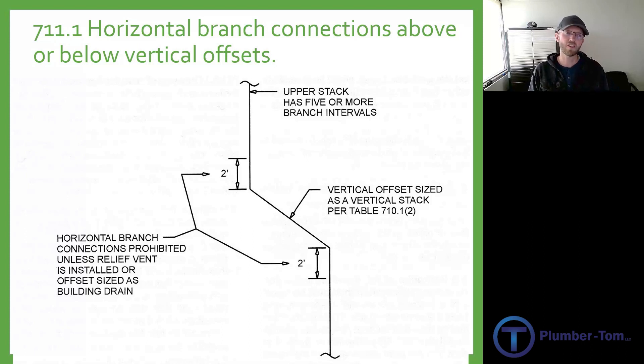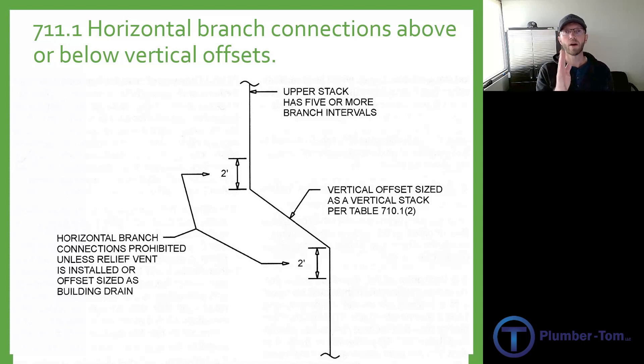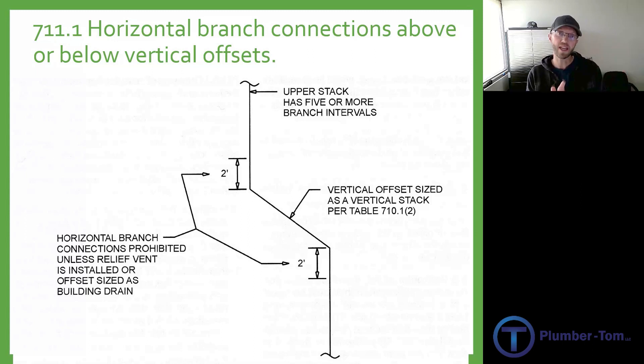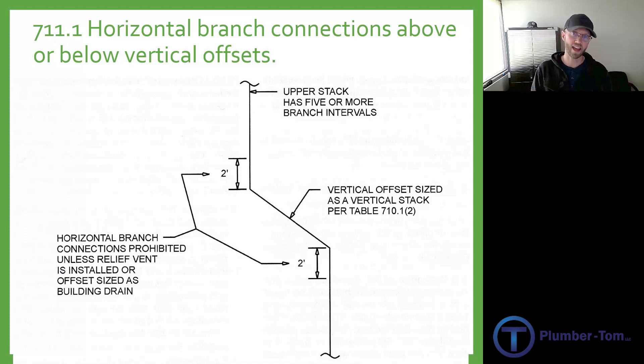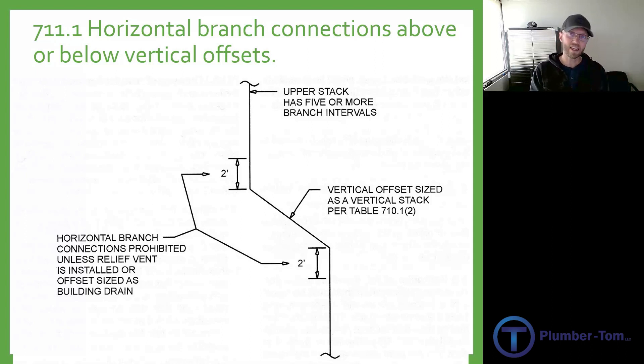7-11.1 talks about horizontal branch connections above or below vertical offsets on a stack. A stack is a vertical drain pipe. As it's coming down it needs to move over — this is called an offset. A vertical pipe is any pipe that is straight up or down to a 45-degree angle; that's still considered vertical. So if we offset that vertical stack with two 45-degree fittings it's considered a vertical offset. 7-11.1 says you cannot connect any horizontal branches within two feet above and two feet below that offset of the stack. The reason is that turbulence and movement of the fluids inside of that offset stack could interrupt the flow of a horizontal branch coming in.